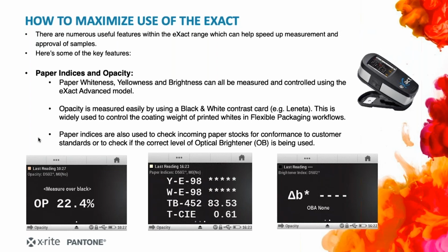printed opacity. Very, very popular function, this. A lot of the time, this is used extensively in the flexible packaging market. Measure a printed white over a contrast card, e.g. Leneta card. Measure it over black background, measure it over white background. We simply get a percentage returned back to us as the overall opacity of that printed coating. The higher the percentage, the more opaque the coating. Again, very useful for quality control, widely used in flexible packaging.